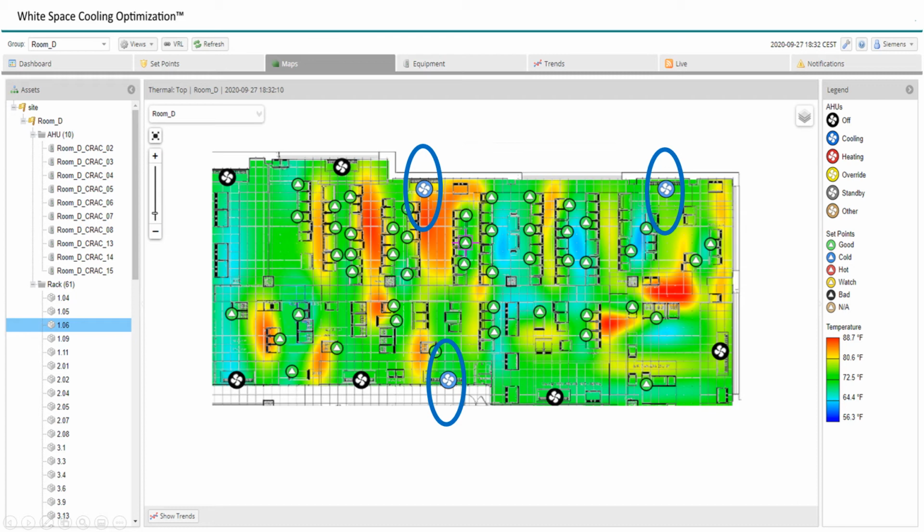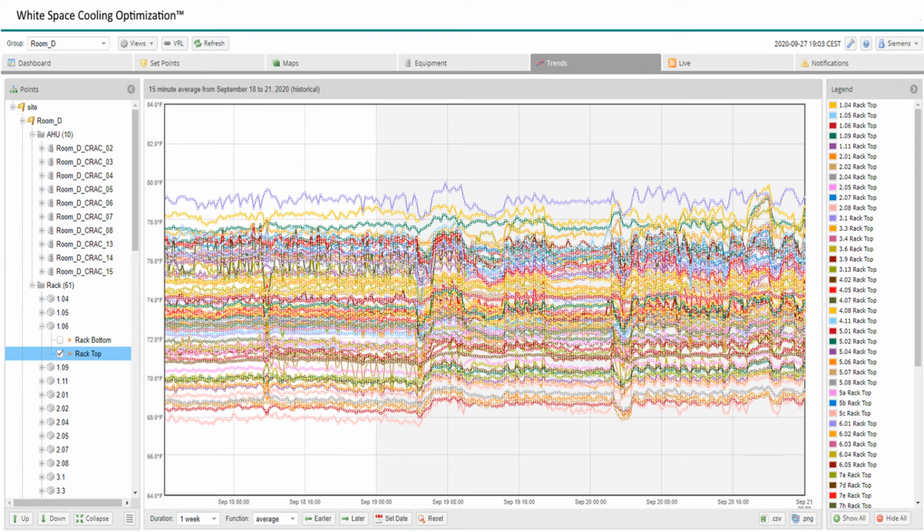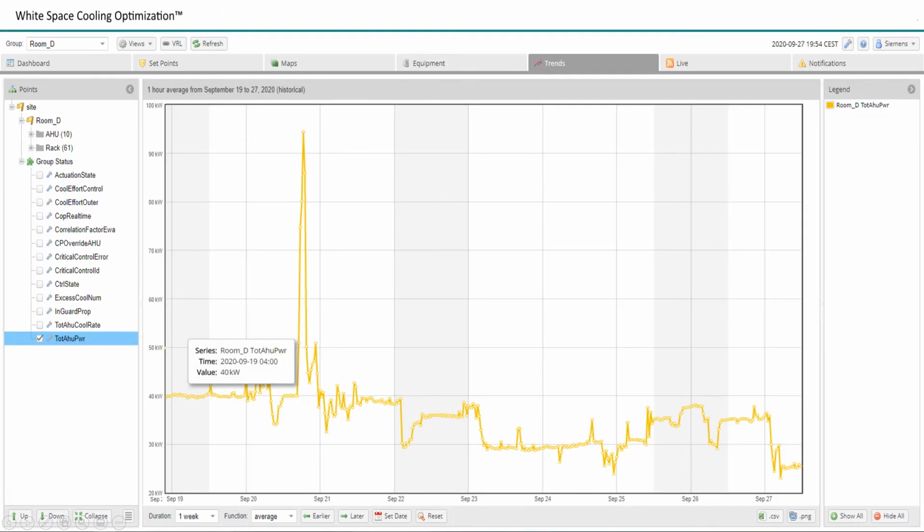Let's look at the trended temperature data post-remediation. Now the temperatures are clustered closer together, and we have virtually no outliers. You can see here that temps across the board are lower than the 80.6 degree limit, which means that the customer is now seeing ideal temperature compliance. And the amazing thing is that they're achieving this result while using less cooling, and the power usage data proves it. Let's take a look at that data.